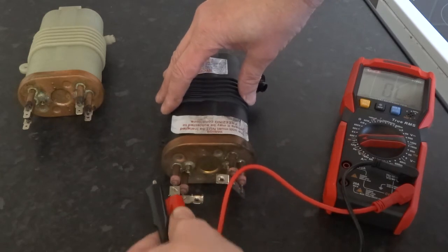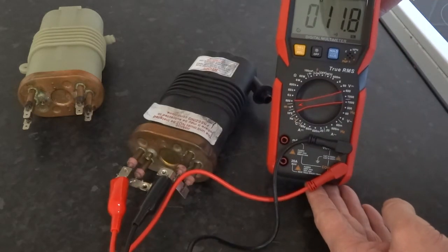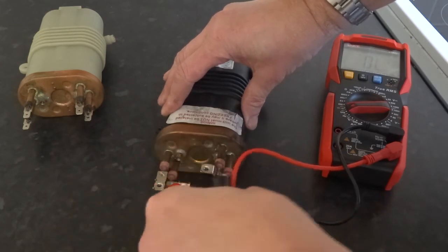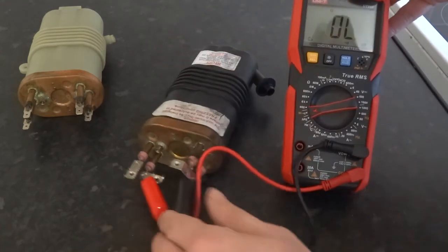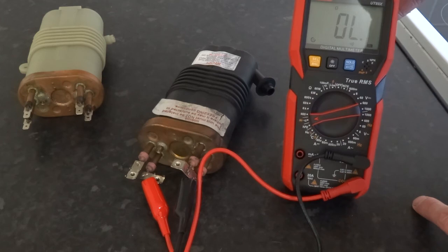Now on the upper element on this one, connected to the neutral bar — 11 ohms on the upper one. Still connected to the same neutral, we're connected to the positive of the bottom one — OL, open loop basically. So there's no continuity in that, no buzzer going and no ohms reading.